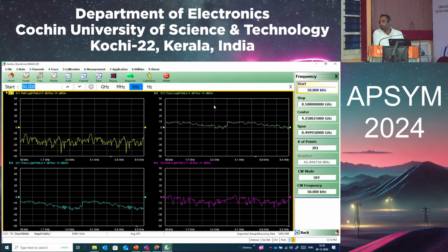measure. Suppose your device is having somewhere around 1 to 3 gigahertz or 1 to 4 gigahertz of frequency range, or any cables or any splitter kind of thing, there will be a frequency range of somewhere around 4 gigahertz. So up to what frequency will you do the calibration? You will do up to 4 gigahertz, or you will be doing the calibration up to whatever the frequency range of the instrument is? What will you be doing?